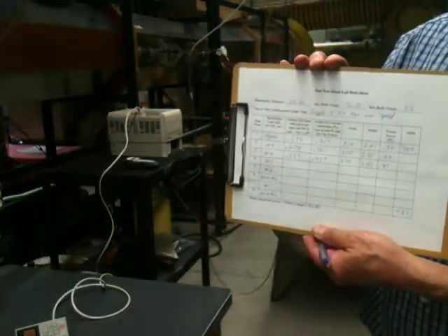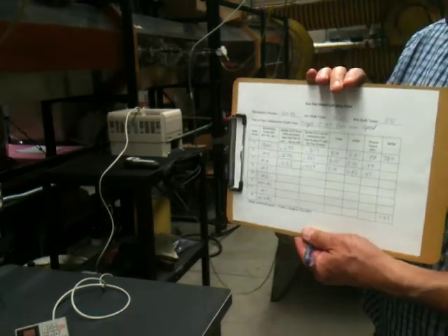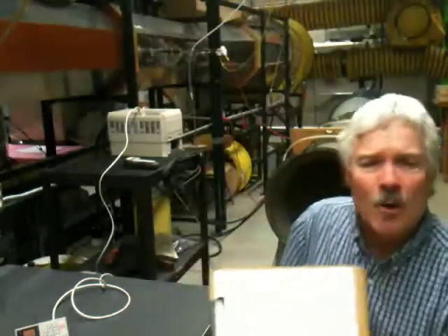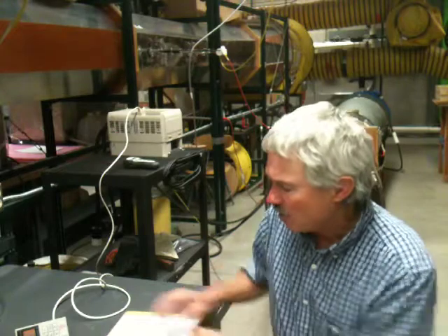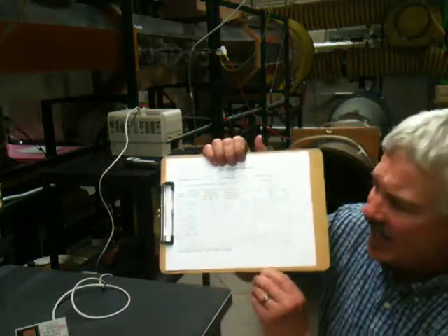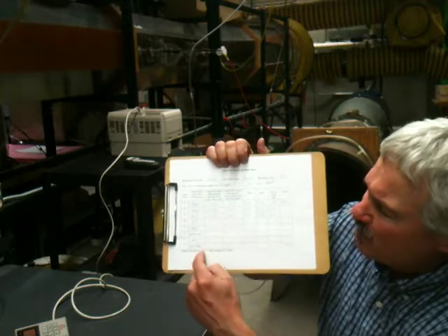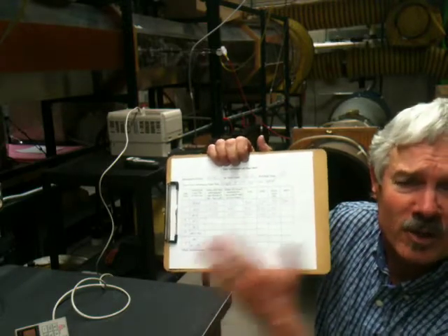And just remember from earlier videos that what we find for our fans running here is that when we're not asking a lot of them, when they're just loping along, the electrical power consumption is fairly constant. And so as the aerodynamic power increases due to the restrictions placed in the box, the operating efficiency ramps up a little bit, okay? So once again, as for the 10 horsepower fan, keep replacing the proper restrictions, recording the data.